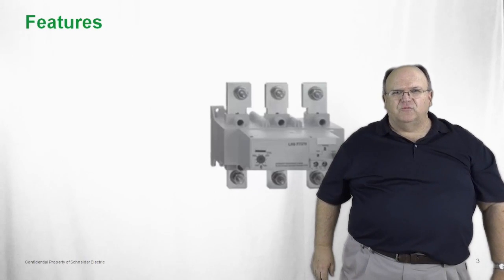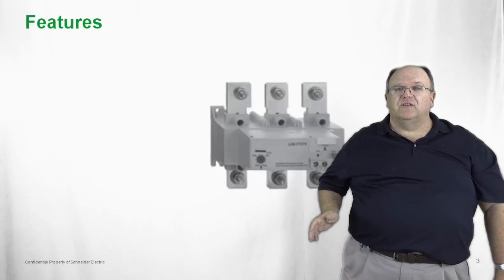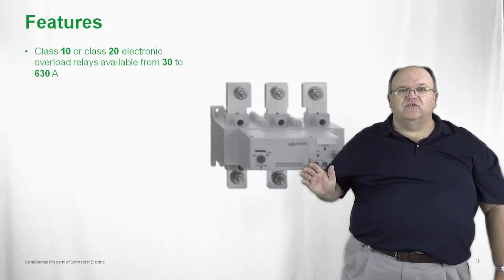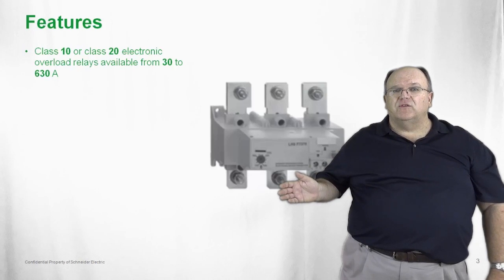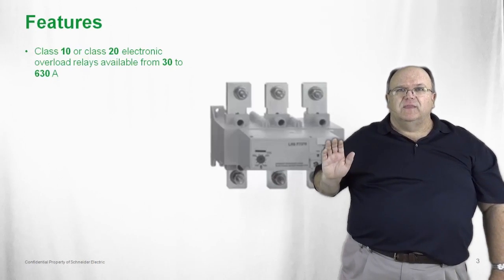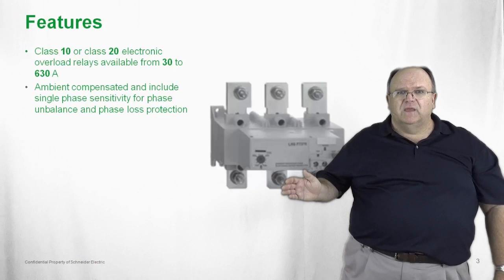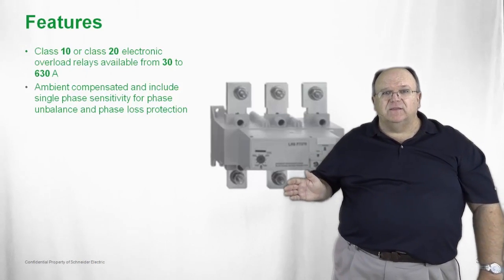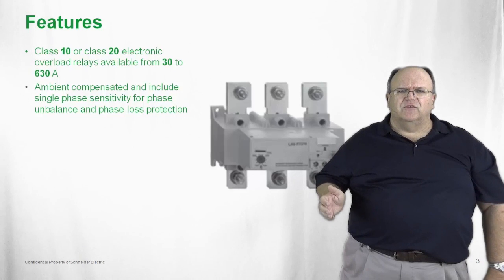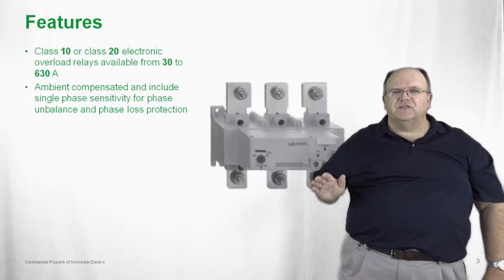Let's take a look at the overload relays in the TeSys F product family. The overloads are the LR9F — a solid-state electronic overload relay. It is available in either Class 10 or Class 20 trip settings, and covers full-load amp currents from 30 amps up to 630 amps, with a very wide adjustment range so you have a minimal number of part numbers. The overloads are also ambient compensated and include single-phase sensitivity to give the motor extra protection from phase loss or phase under-voltage conditions.